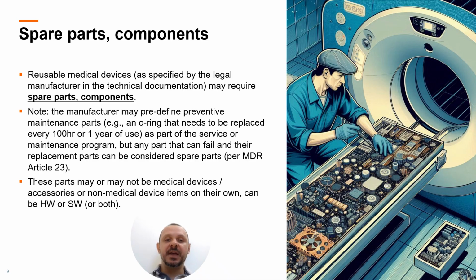Reusable medical devices, as specified by the legal manufacturer in the technical documentation, may require spare parts or components. So typically these are reusable devices that need maintenance or certain parts will wear out. The manufacturer may predefine preventive maintenance parts, for example, an O-ring that needs to be replaced every certain period of time as part of the service or maintenance program, but any part that can fail and the replacement parts can be considered spare parts according to MDR Article 23. These parts may or may not be medical devices, accessories, or non-medical devices on their own, and these can be hardware or software or both.